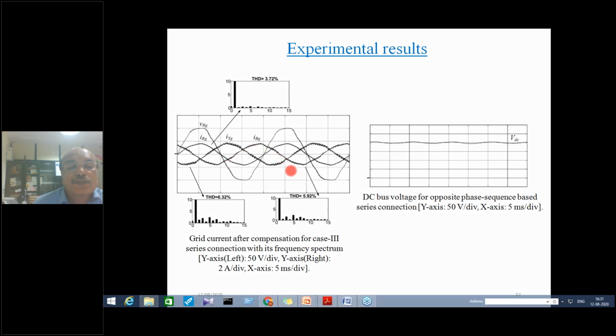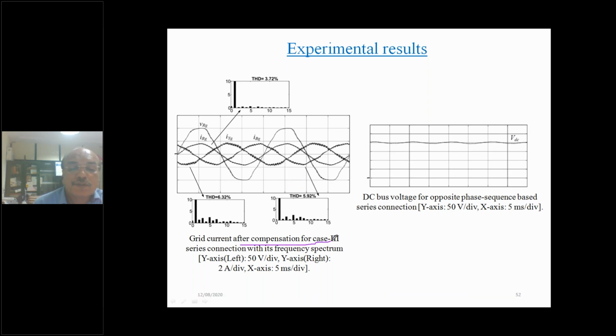See here, these 3 currents shown after compensation for case 3 — current R, Y, and B — all look the same, and this is the grid voltage. You can see it is maintaining UPF, unity power factor. This unity power factor is achieved, we are able to maintain grid current balance, and the THD part is also reduced.